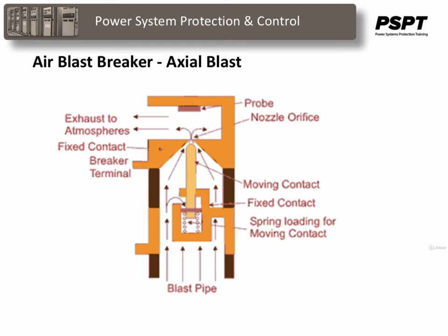In axial blast circuit breakers, the moving contact is held in contact with a fixed contact with the help of spring pressure, as shown in this slide. There is a nozzle orifice in the fixed contact, which is blocked by the tip of the moving contact when it is in the normally closed position. When a trip occurs, high pressure air is introduced into the arcing chamber.